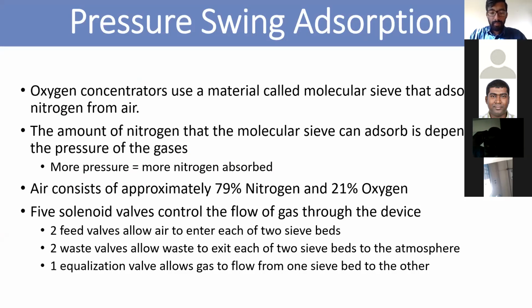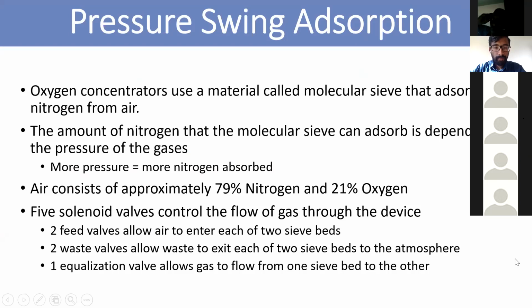So air consists of 79% nitrogen and 21% oxygen, atmospheric air. So that's how it works. The Sieve tank normally absorbs nitrogen and lets go of the oxygen, so you get more oxygen output. Normally, when you talk about oxygen concentrator, you're going to see 5 solenoid valves that control the flow of the gas through the device: 2 feed valves that allow the air to enter, and 2 more to send out waste. Sometimes you're going to see only 3: 2 combination feed and waste valves, and 1 equalizer valve.